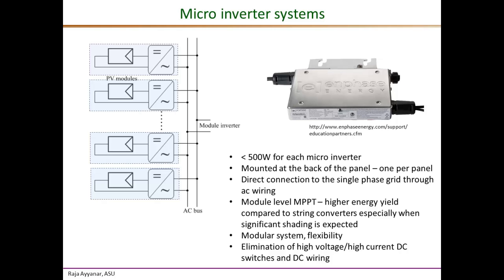The drawbacks of microinverters include cost — they do not scale up cost-effectively. They also tend to have slightly lower efficiency, around 95% CEC efficiency versus 97% for string inverters and 98% for central inverters. Since microinverters are mounted on the PV module, they are subjected to the same harsh environments — high temperatures, large temperature cycling, moisture, and so on. If they do fail, since they are placed on the rooftop, they are also fairly difficult to service.